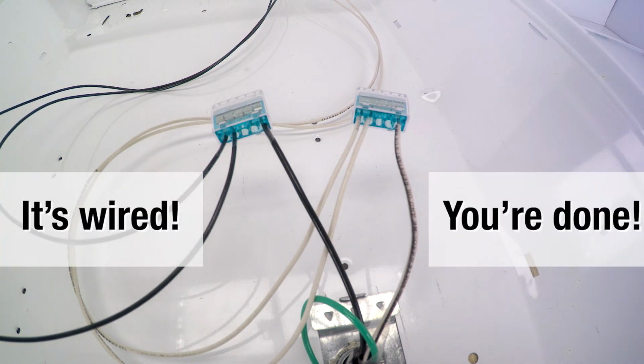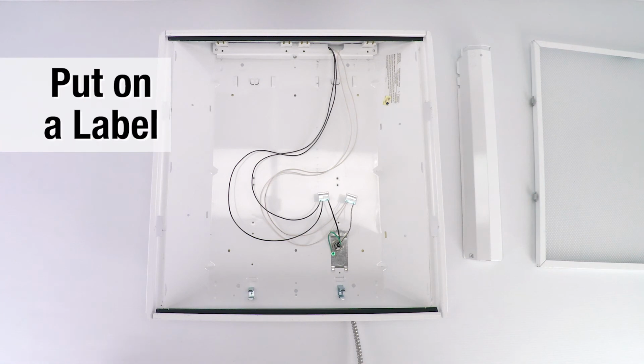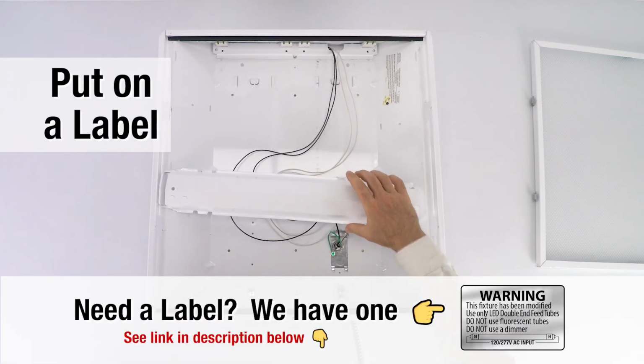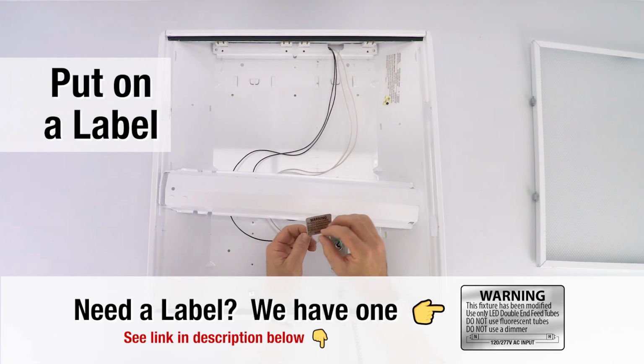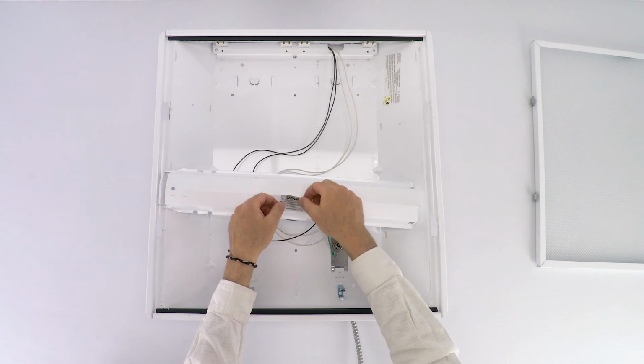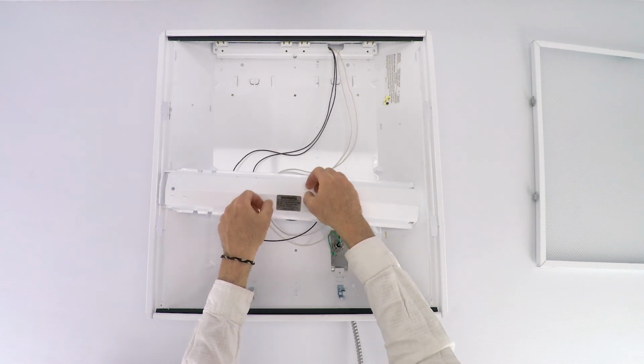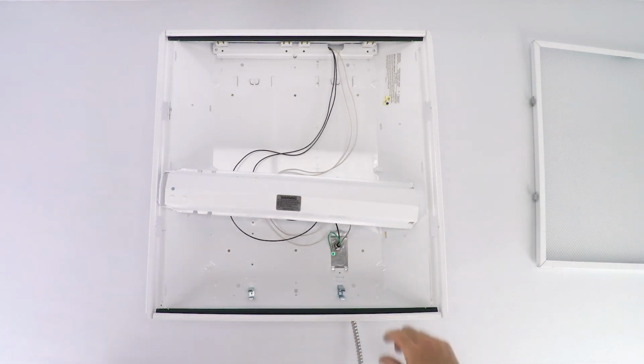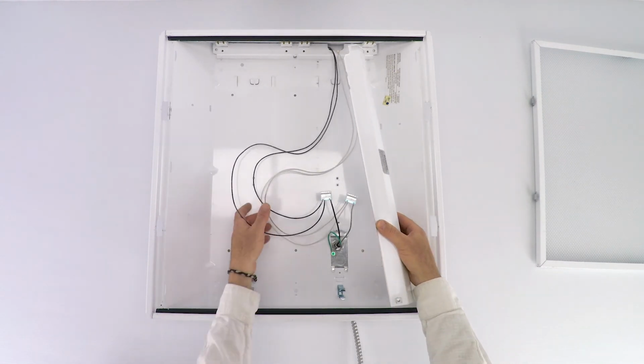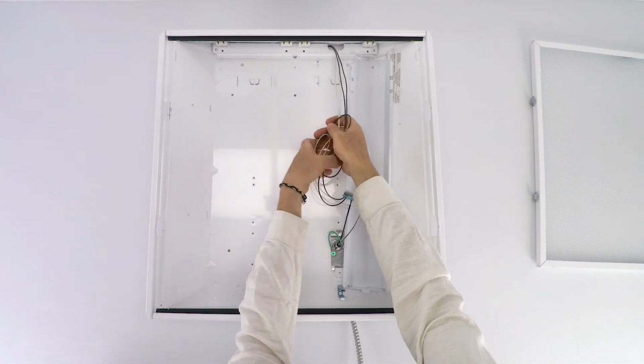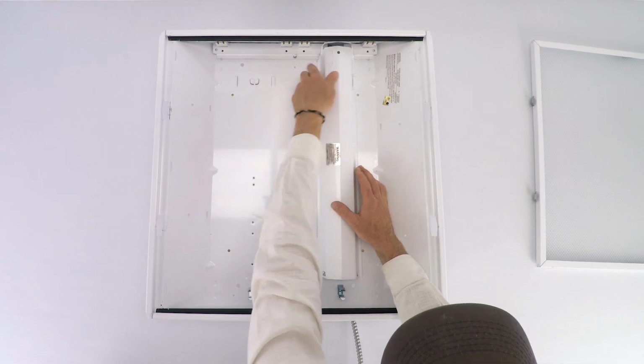It's wired. You're done. Now, put a label on the cover where the ballast was. Make sure you get a label there so people know in the future that this light fixture has been converted to a double-end LED tube. And they won't get all confused and try to put fluorescent light bulbs in there. Now, all you need to do is cover up all the wires, tuck them underneath, make sure they're not pinched, and you're kind of ready for the next step.